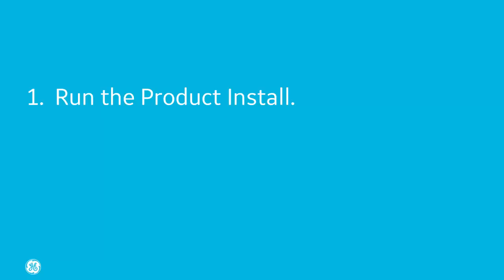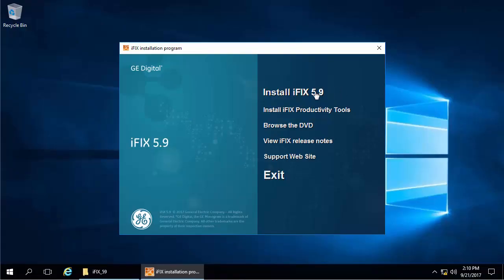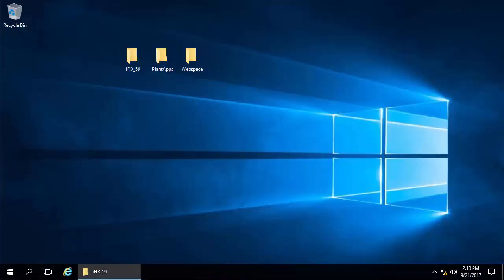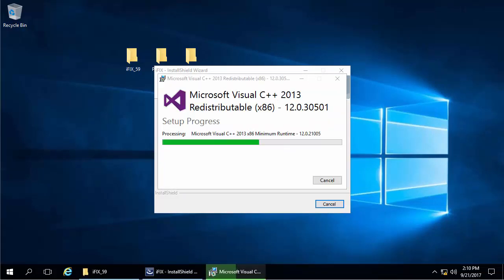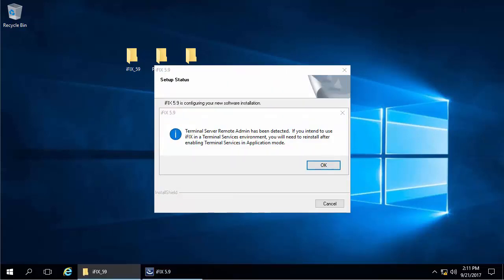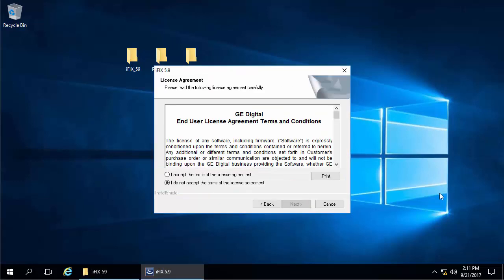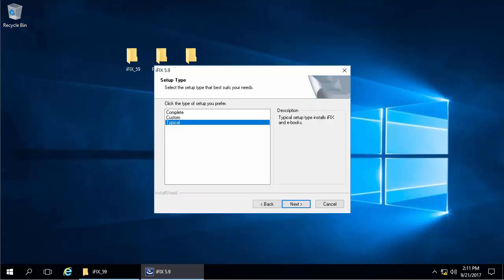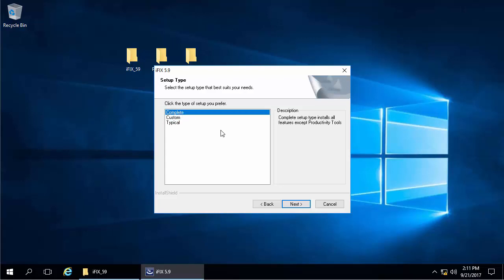Step one: run the product install. Click the iFix 5.9 link from the install splash screen. If you haven't installed the latest Microsoft Visual Studio redistributables, this runs automatically. A message box appears — a terminal server remote admin is also detected — just click OK to continue. A welcome screen will appear, then the license agreement. Accept the terms to continue. Next, select the type of iFix install.